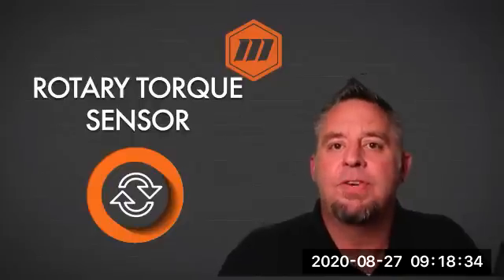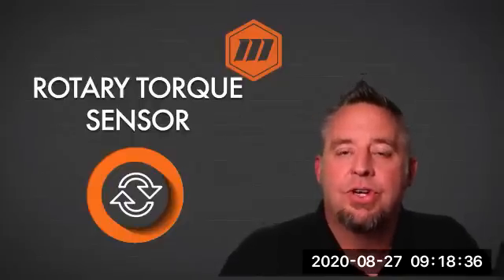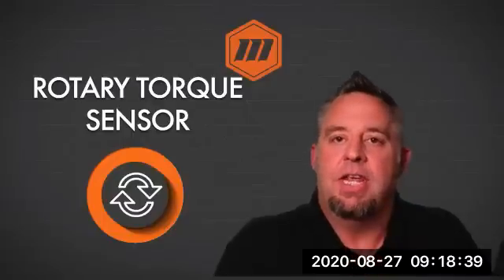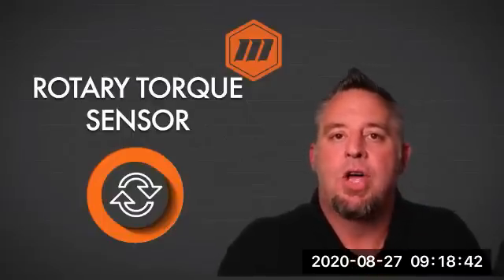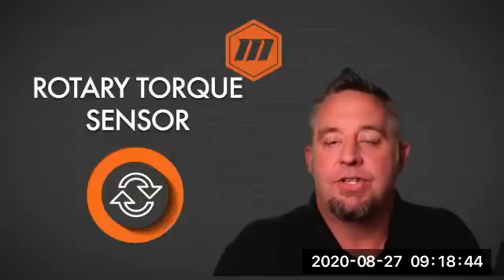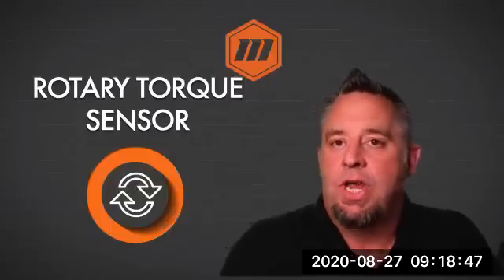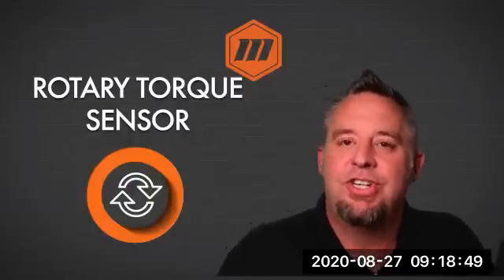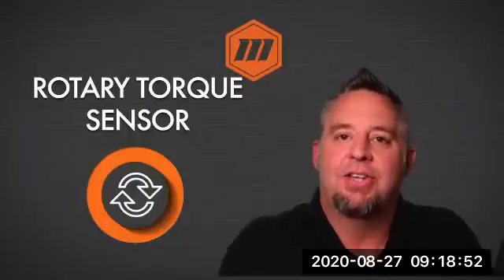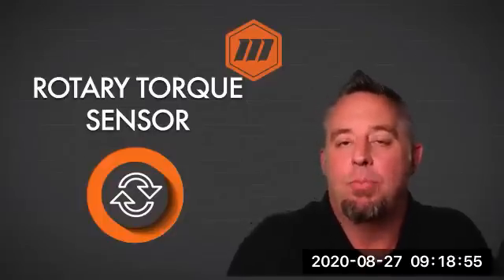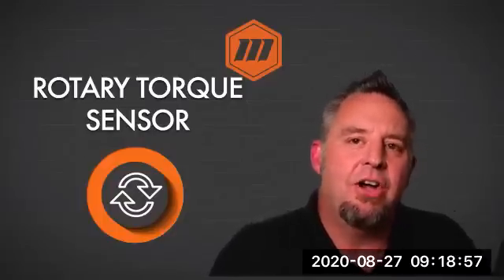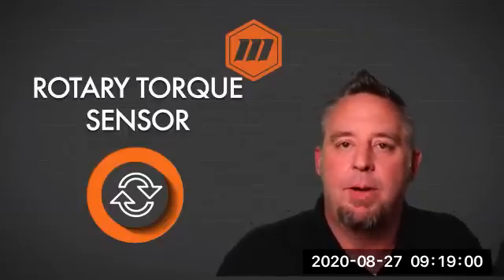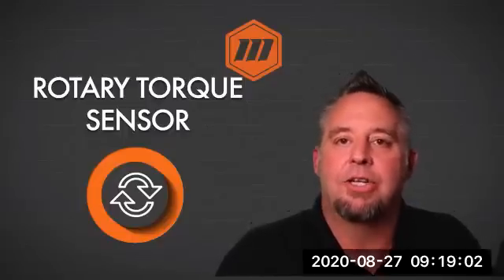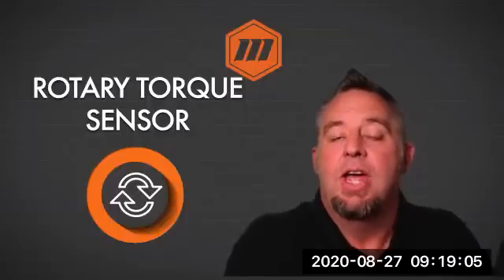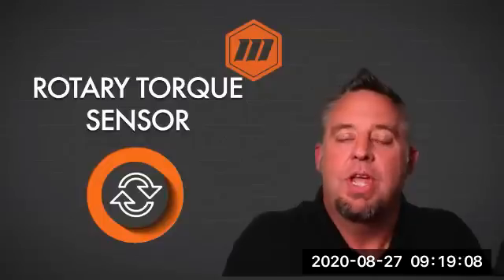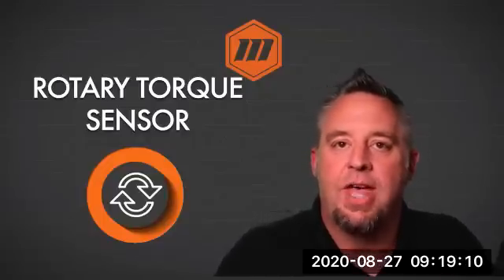Now, there are a couple of different styles of the rotary torque sensor. We have the rotary sensor, and we also have a rotary sensor that will also give us an angle. In every circle we have 360 degrees of rotation, so that gives us a reading at every angle point we can see. In our analyzer software, you can set that up to look at a specific angle value, and if you want to do a torque plus angle, you could use the rotary sensor for that as well.